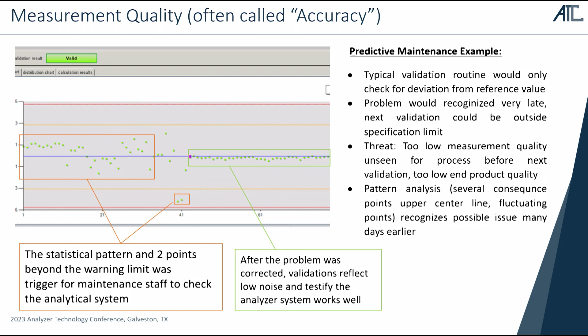Then after 7 or 8 validations, you see the values changing a lot. There was a high spread of the data, so the repeatability was getting weaker and weaker. And then suddenly you see out points which are violating limits. Normally a technician would only notice once a limit was violated. What software can do is analyze the complete pattern beforehand and inform the user that there might be a problem, so you can start investigating earlier where the issue comes from. So this is the way to look at the quality, often called accuracy, of a measurement, but also to better plan your preventive maintenance schedule.